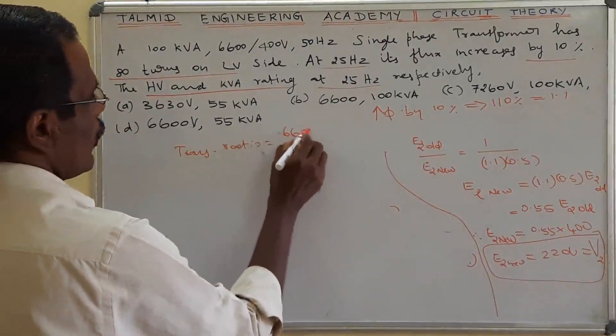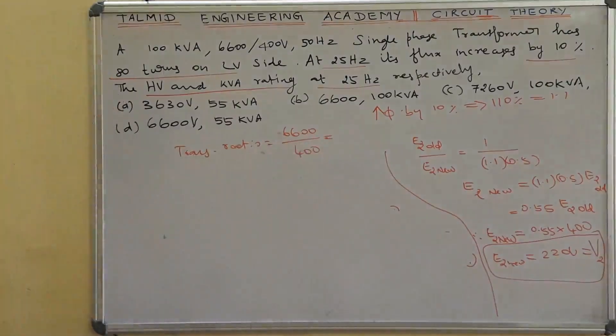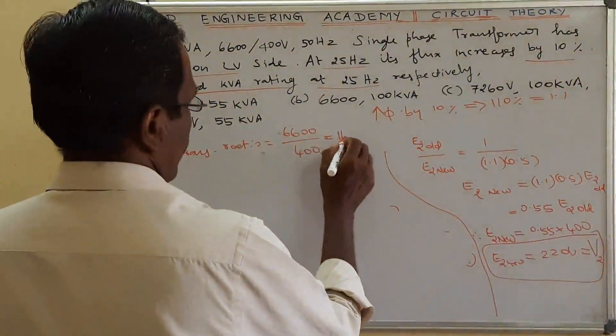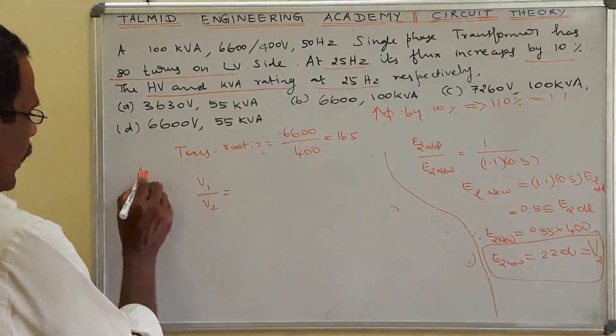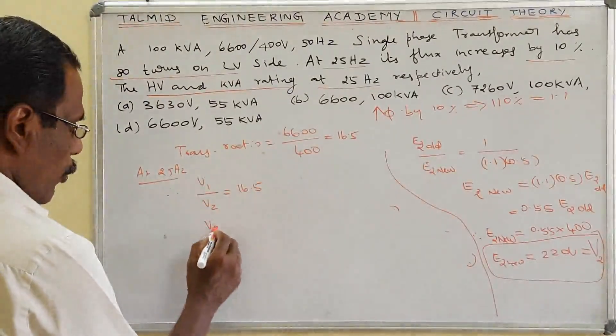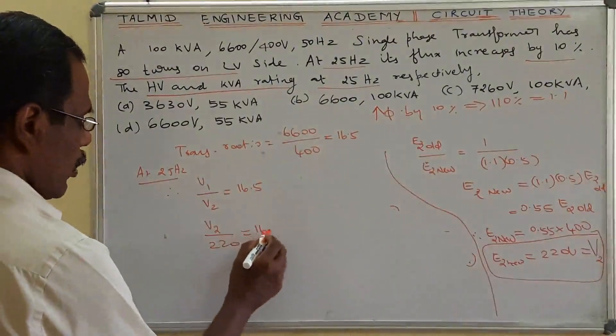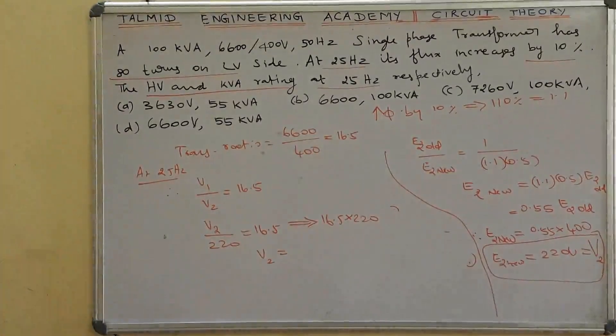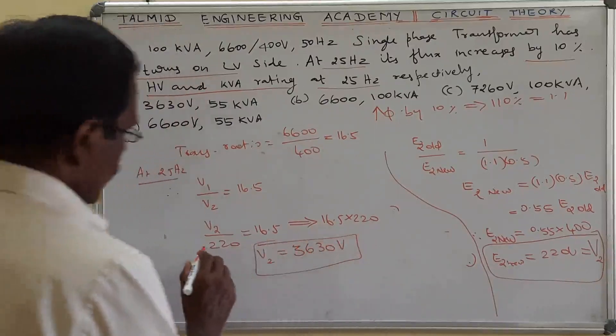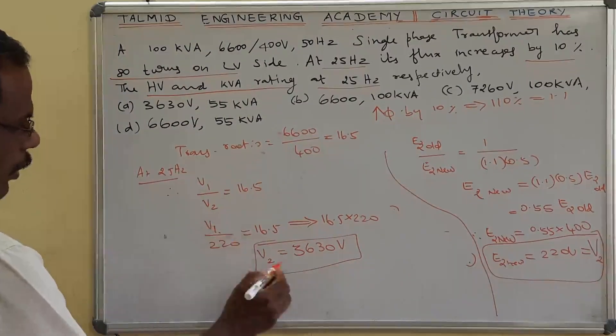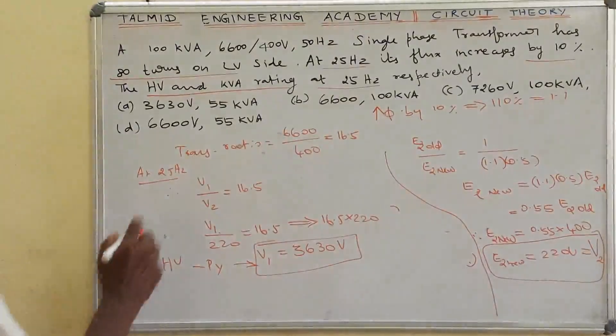The turns ratio is N1/N2 = 6600/400 = 16.5. Therefore V1/V2 at 25 Hz: applying the same ratio, V1 = 16.5 × V2_new = 16.5 × 220. Therefore the HV side — that is primary voltage — HV side voltage is 3630, approximately 3600 volt. This is the HV rating.